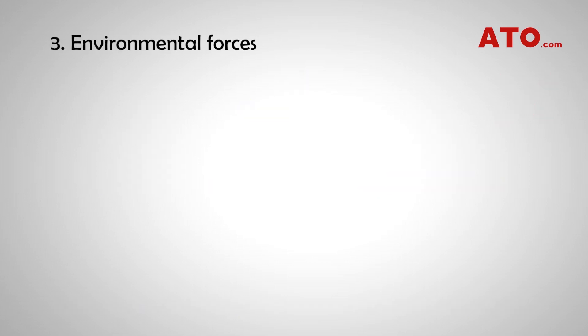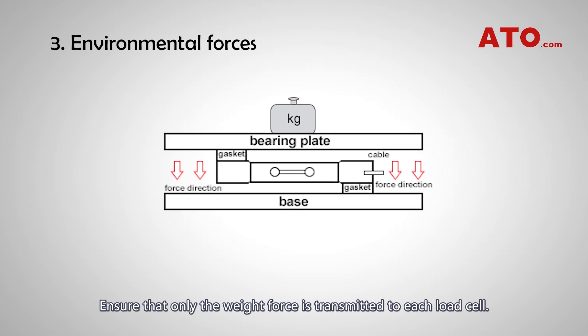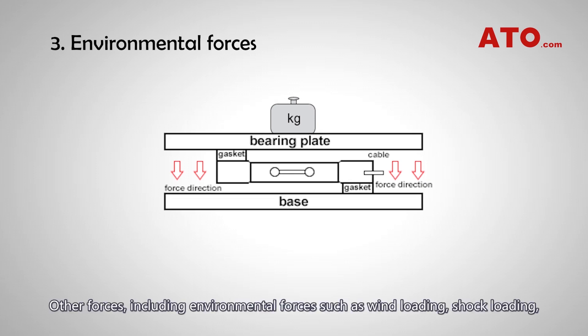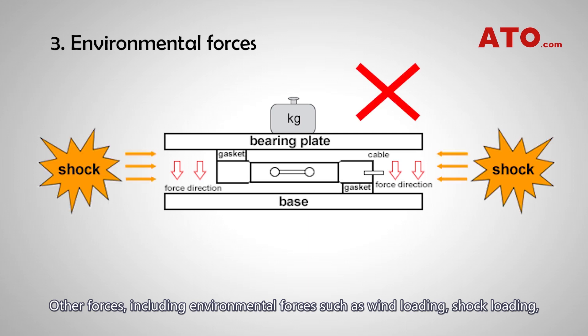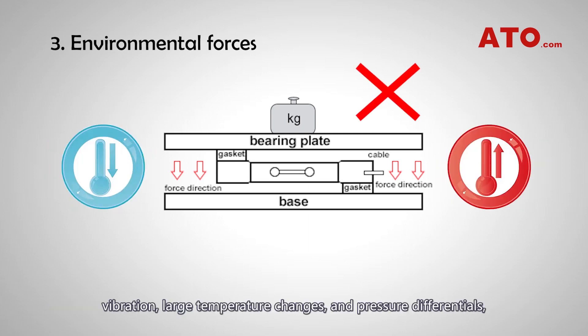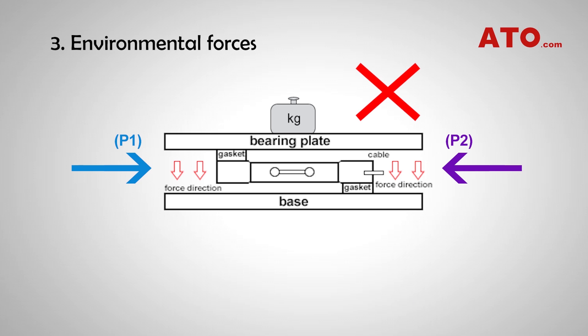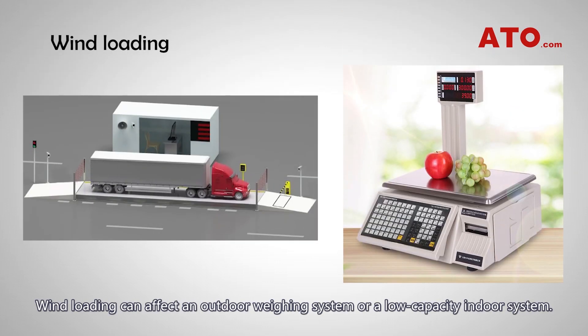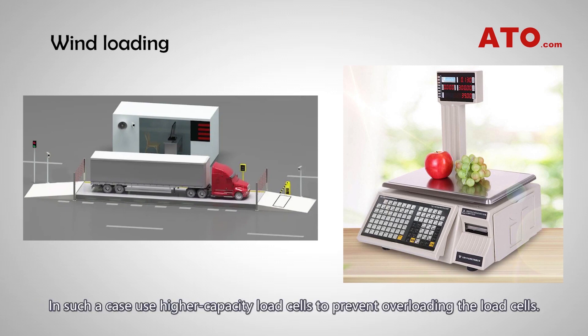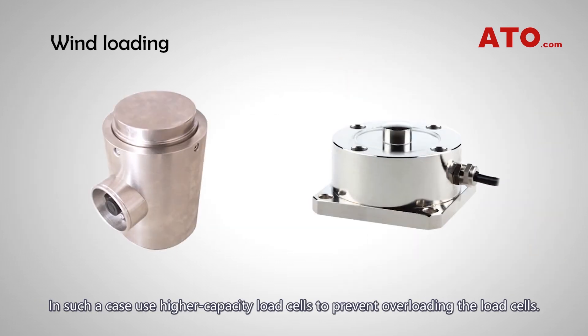Environmental forces. Ensure that only the weight force is transmitted to each load cell. Other forces, including environmental forces such as wind loading, shock loading, vibration, large temperature changes, and pressure differentials, can produce errors in the load cell signal. Wind loading can affect an outdoor weighing system or low-capacity indoor system. In such a case, use higher capacity load cells to prevent overloading.